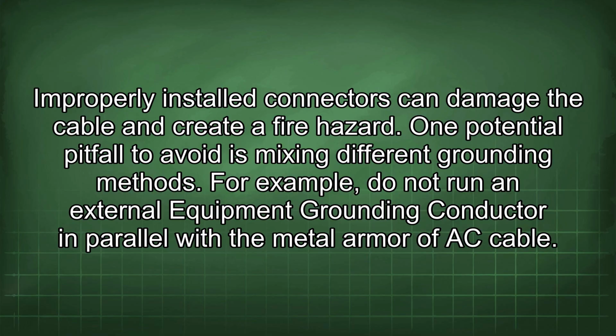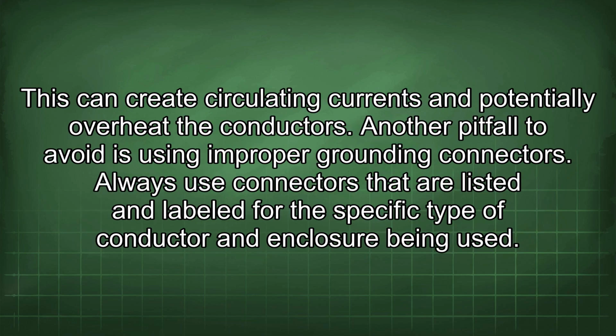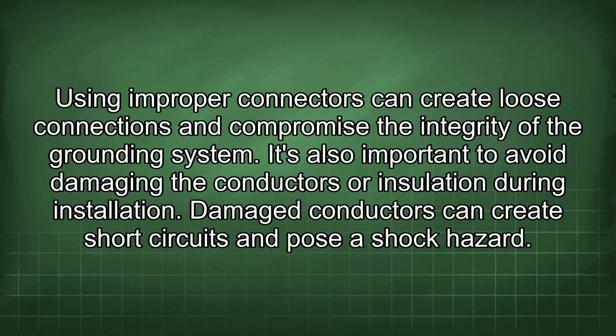One potential pitfall to avoid is mixing different grounding methods. For example, do not run an external equipment grounding conductor in parallel with the metal armor of AC cable. This can create circulating currents and potentially overheat the conductors. Another pitfall to avoid is using improper grounding connectors. Always use connectors that are listed and labeled for the specific type of conductor and enclosure being used. Using improper connectors can create loose connections and compromise the integrity of the grounding system.